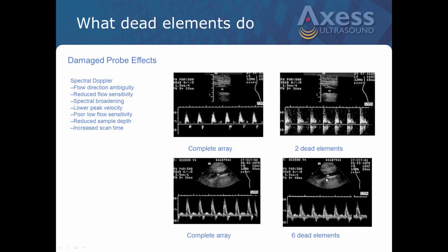We've got a question here from Chandra: can dead elements individually be repaired? Again, no, that's impossible. It's too costly to do even if you could, because you basically have to destroy the array stack in order to go in there and replace an individual element. So it's far better to just replace the entire array stack.